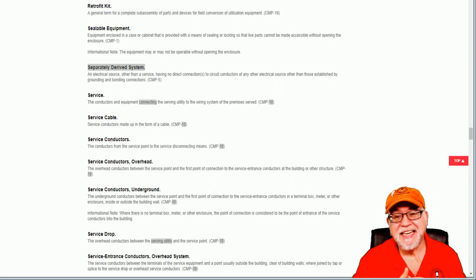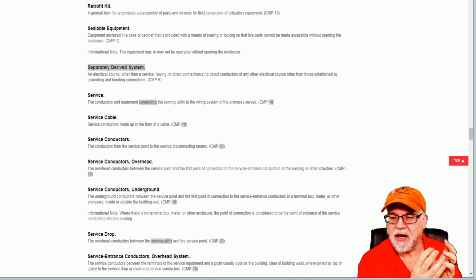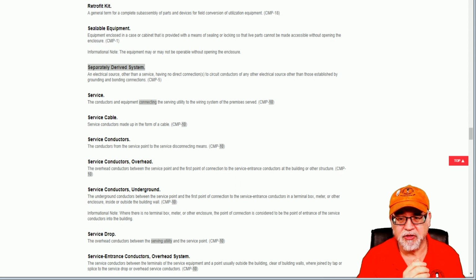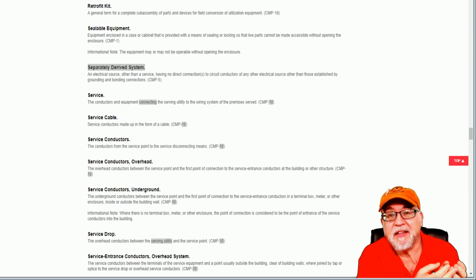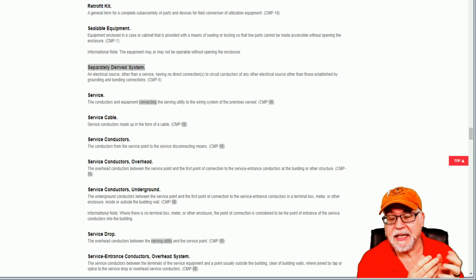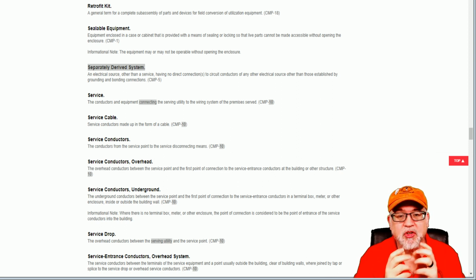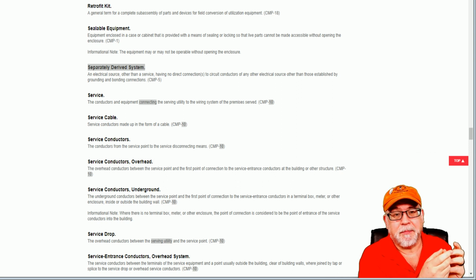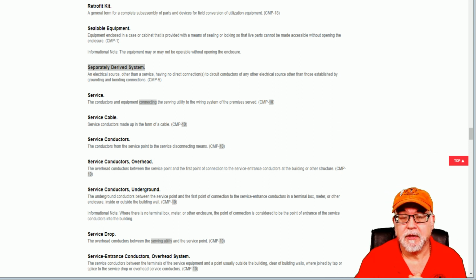Why is that important? Because you need to remember that if it's a separately derived system, because of full transfer and there's no direct connection, then you have to treat it as if it was kind of like a service, even though it's not a service. You have to treat it and establish a grounding electrode system there and do everything a little bit different, okay? Otherwise, you can get circulating currents and create a hazard. Now, if it is not a separately derived system, then it is literally just another piece of equipment, just like, let's say, a range or HVAC unit. It's just another piece of equipment. And again, you have to treat it accordingly. So it's important to know, and you don't want to do things that you would do for a separately derived system to a non-separately derived system, because you can create a serious hazard. Okay? So it's important to understand whether or not you're dealing with a separately derived system or not.